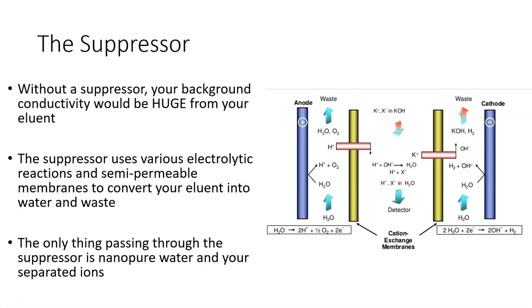The suppressor uses various electrolytic reactions and semi-permeable membranes to convert your eluent into water and waste. The example on the right here shows a sample leaving an anion exchange analytical column in a potassium hydroxide eluent. The electrolytic reactions taking place on the sides convert your base into water and your cations into waste. It's not super important to understand all of these reactions, but it's important to understand that the suppressor is essential to getting good conductivity measurements.